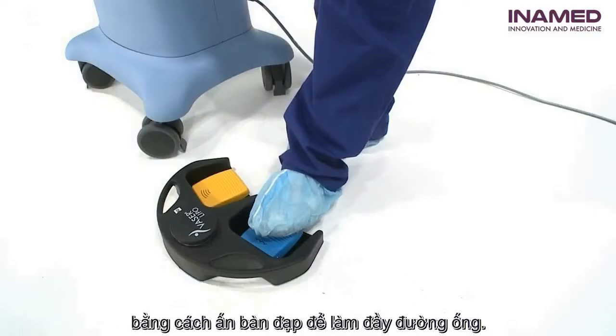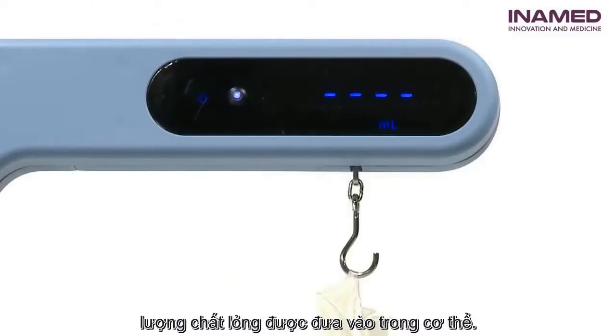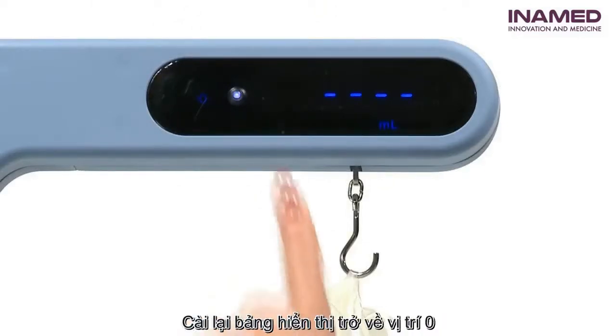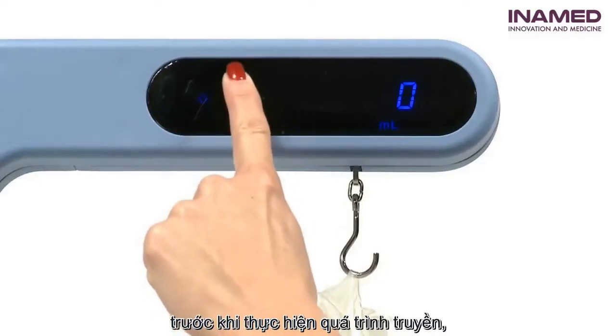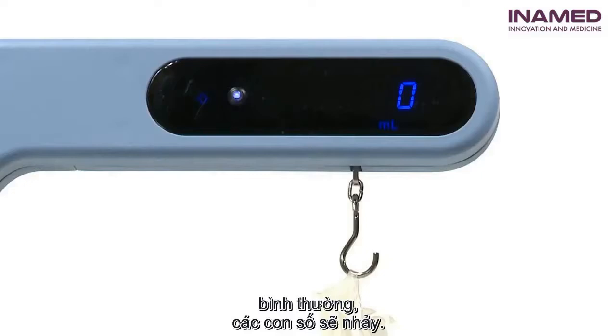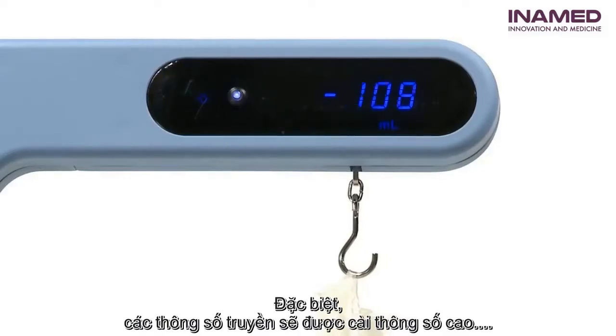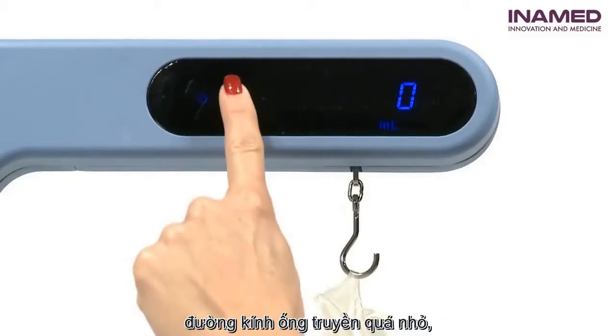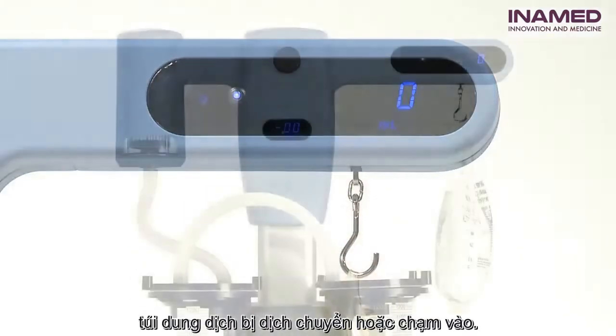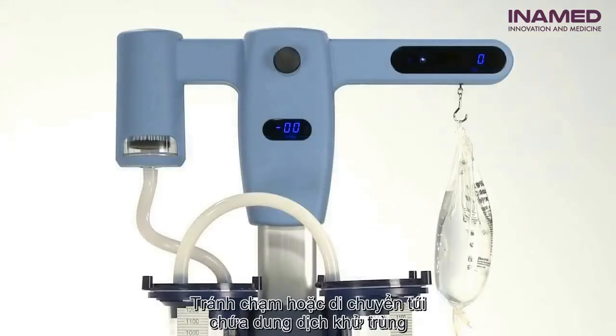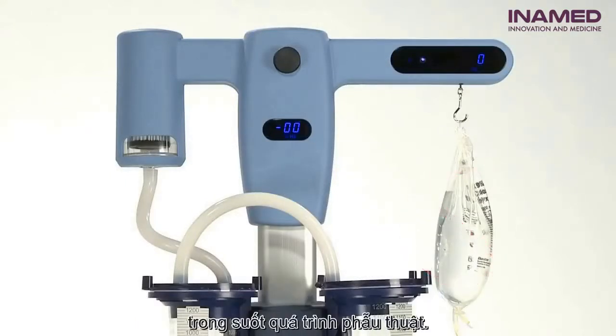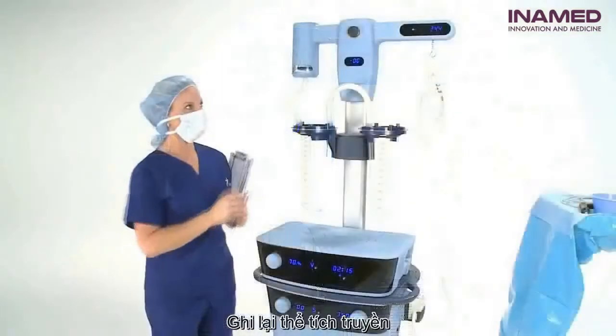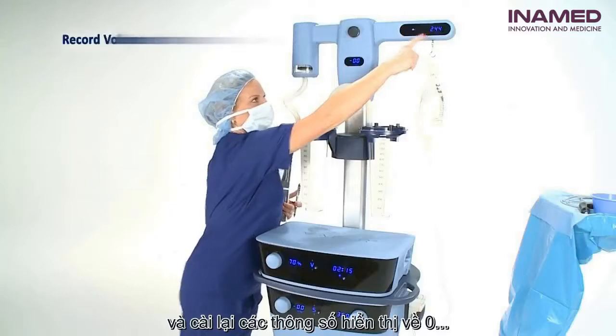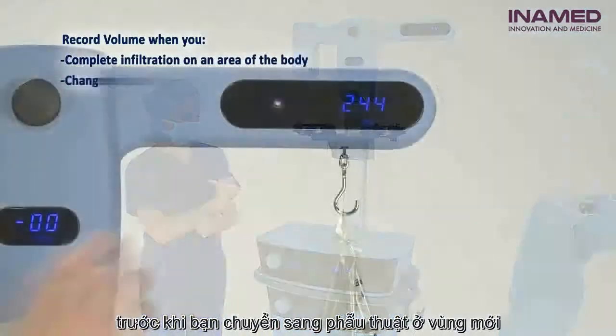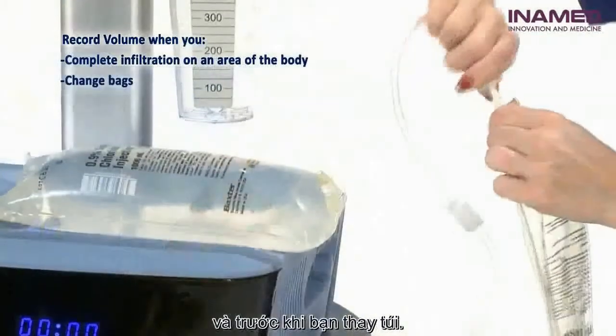Prime the infiltration tubing by depressing the foot switch to fill the line. The infiltration volume display shows the amount of fluid being infused into the patient. Reset the display to 0 before initiating the infiltration process. It is normal for the numbers to jump, especially if the flow rate is set at a high rate, if the infiltration tubing diameter is very small, or if the fluid bag is moved or touched. Avoid touching or moving the sterile fluid bag during the infiltration process. Be sure to record the infiltration volumes and reset the volume display to 0 before you begin infiltration on a new area and before you change bags.